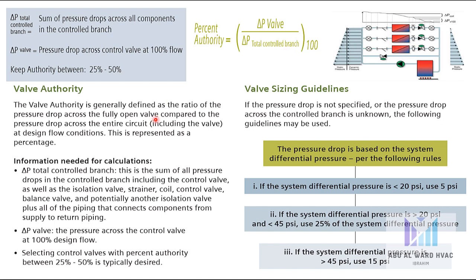The information needed for calculation is ΔP total controlled branch and ΔP valve. We should select a control valve with percent authority between 25% and 50%, which is the desired range. For valve sizing guidelines: use ΔP for valve of 5 PSI if system differential pressure is less than 20 PSI; use 25% of system differential pressure if greater than 20 PSI; and use 15 PSI if the system differential pressure is greater than 45 PSI.